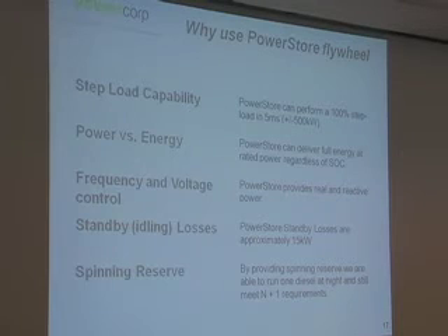Frequency and voltage, Russell touched on that earlier, with the flywheel providing both real and reactive power. Now, I know one of the questions that was asked of Norm is what the parasitic load is. In our application, because we put all the power electronics and the flywheel in a 40-foot container and it's 50 degrees outside, we require a fair bit of cooling load to keep all the power electronics within an acceptable range. So at this particular site, we're seeing about 15 kilowatts. People will say that's quite high, and I guess it is, but the benefits that the flywheel provides far outweigh that 15 kilowatts.